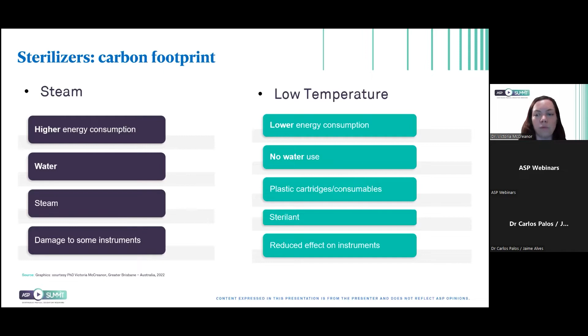And then the low temperature solution has generally a much lower energy consumption, and doesn't use any water. But from a carbon footprint perspective, it's important to take into account the plastic cartridges and consumables that are used in low temperature sterilizers, and also the sterilant. There's also a reduced effect of damage to instruments. So I'll talk a little bit more about how to take all of that into account.